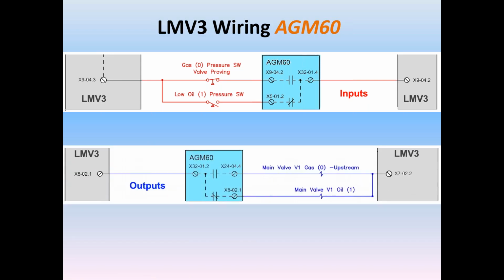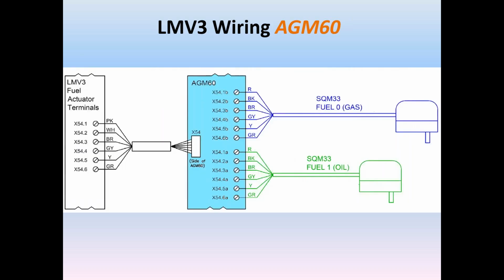In the same fashion, the LMV3 can be used for outputs, so that if the LMV3 energizes 821 as an output, the AGM60 takes it in, and then it outputs it to V1 gas in the case of fuel 0, or V1 oil in the case of fuel 1. And then 722 is the common neutral. So the AGM60 sorts out the inputs and outputs based on the fuel. It also directs the fuel actuator output. Terminal X54 goes to the AGM, and then the AGM sorts out whether it goes to fuel 0, in this case gas, or fuel 1, in this case oil. X54B is 0, X54A is fuel 1.